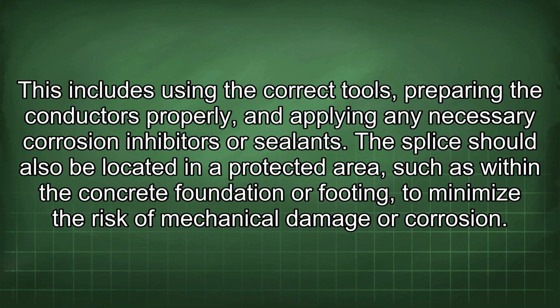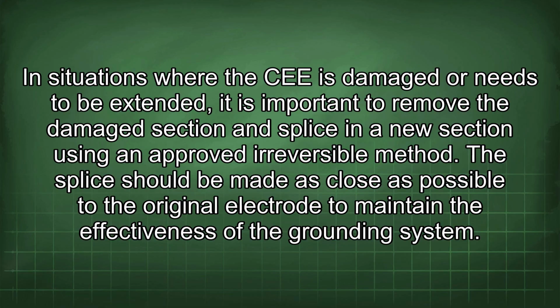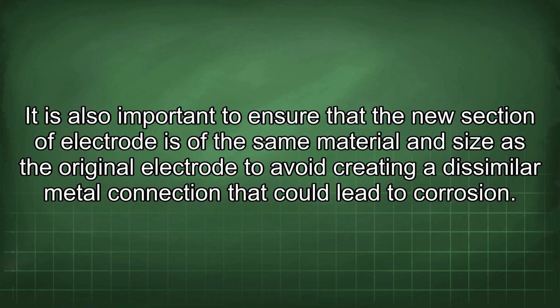The splice should also be located in a protected area, such as within the concrete foundation or footing, to minimize the risk of mechanical damage or corrosion. In situations where the CEE is damaged or needs to be extended, it is important to remove the damaged section and splice in a new section using an approved irreversible method. The splice should be made as close as possible to the original electrode to maintain the effectiveness of the grounding system. It is also important to ensure that the new section of electrode is of the same material and size as the original electrode to avoid creating a dissimilar metal connection that could lead to corrosion.